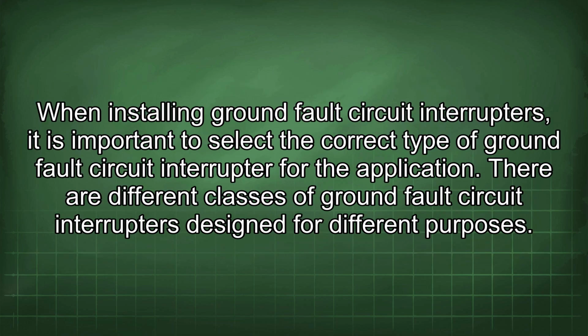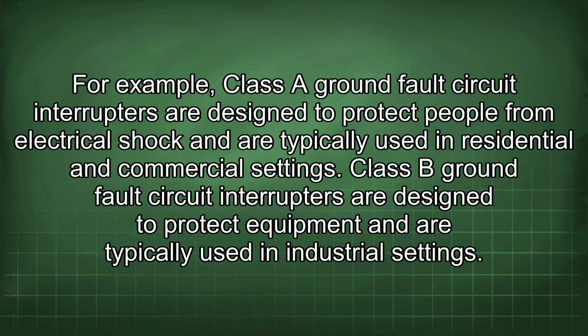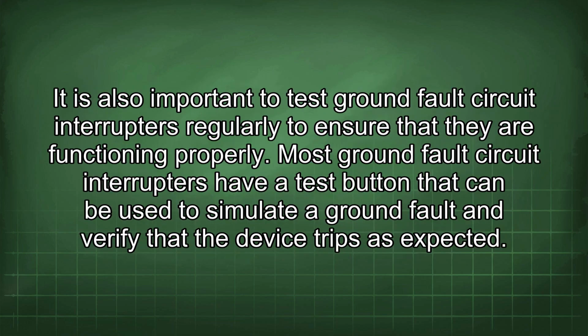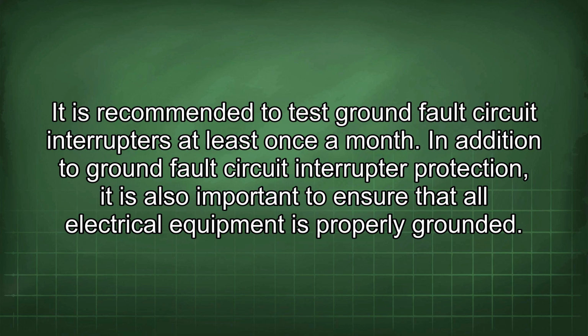When installing ground fault circuit interrupters, it is important to select the correct type of ground fault circuit interrupter for the application. There are different classes of ground fault circuit interrupters designed for different purposes. For example, Class A ground fault circuit interrupters are designed to protect people from electrical shock and are typically used in residential and commercial settings. Class B ground fault circuit interrupters are designed to protect equipment and are typically used in industrial settings. It is also important to test ground fault circuit interrupters regularly to ensure that they are functioning properly. Most ground fault circuit interrupters have a test button that can be used to simulate a ground fault and verify that the device trips as expected. It is recommended to test ground fault circuit interrupters at least once a month.